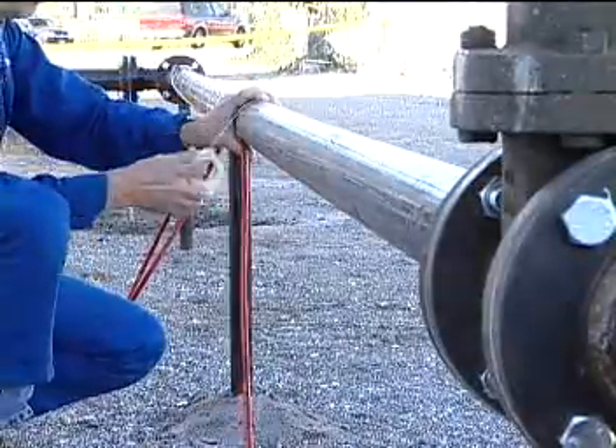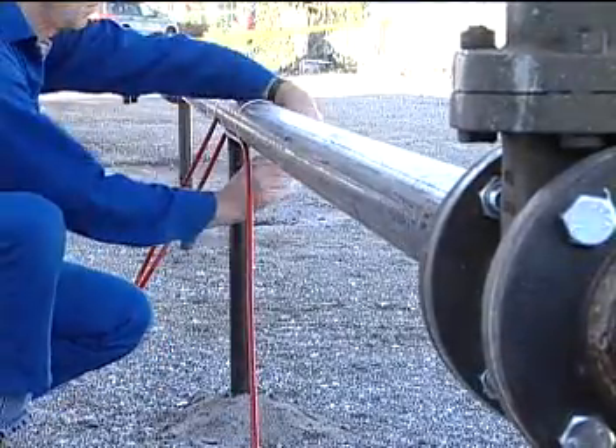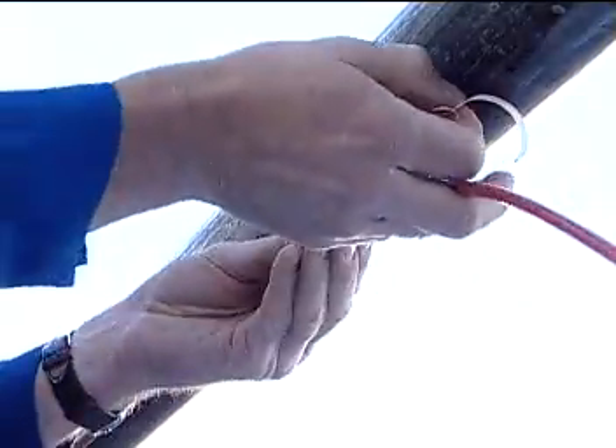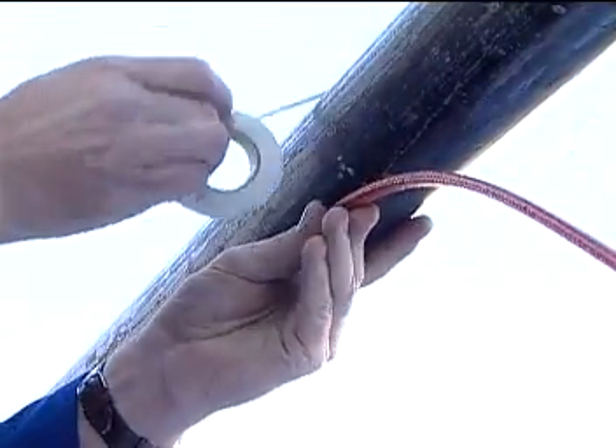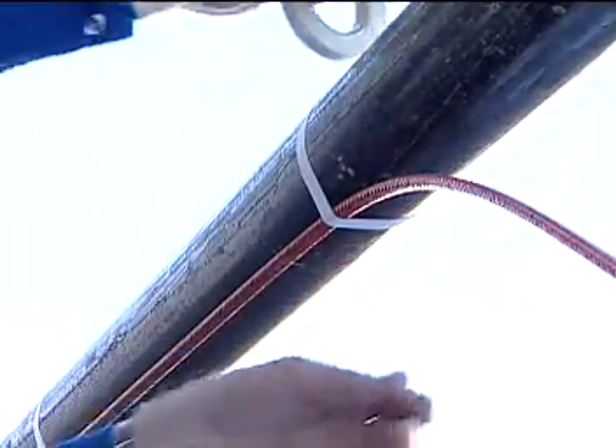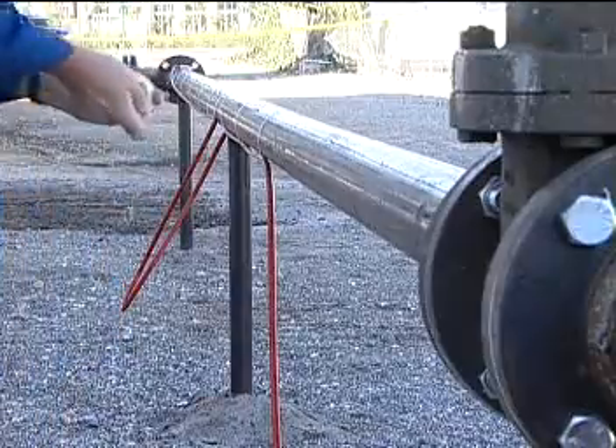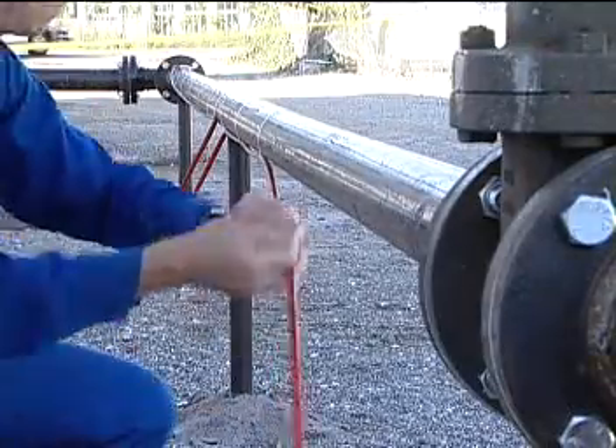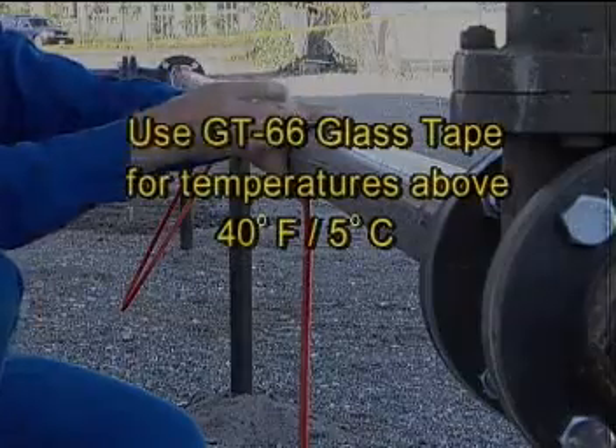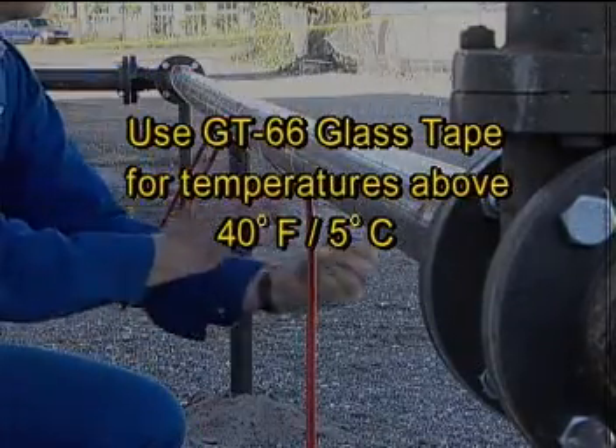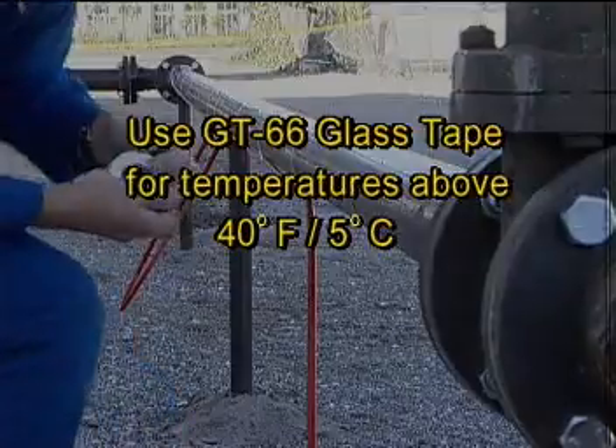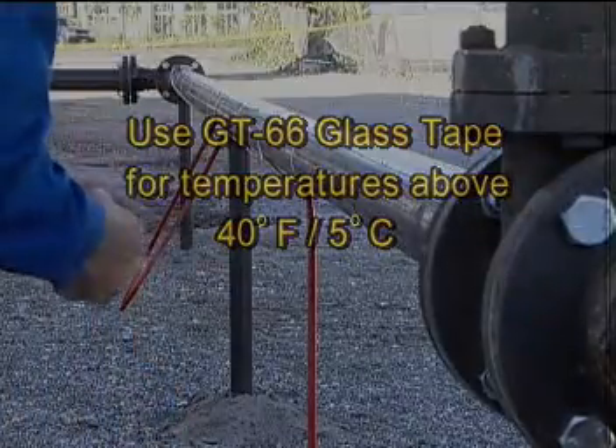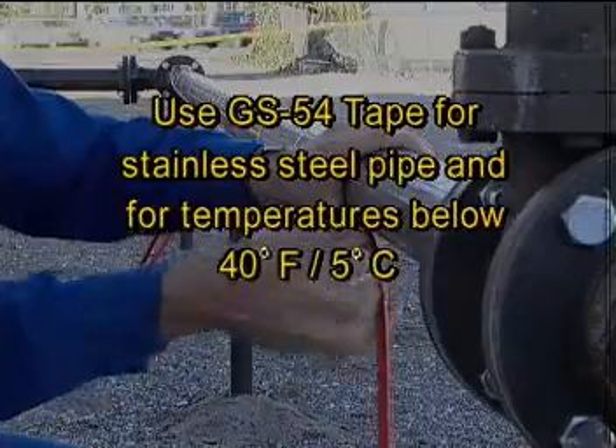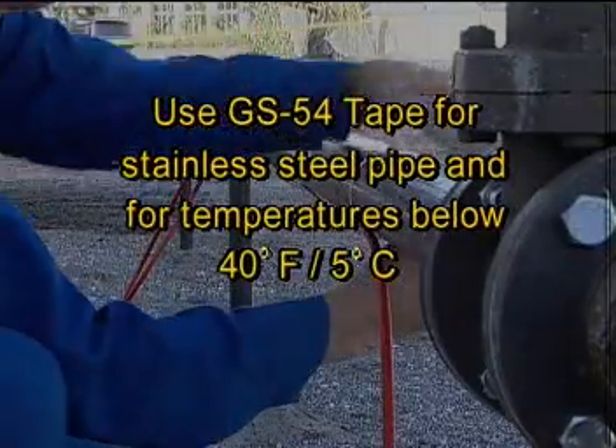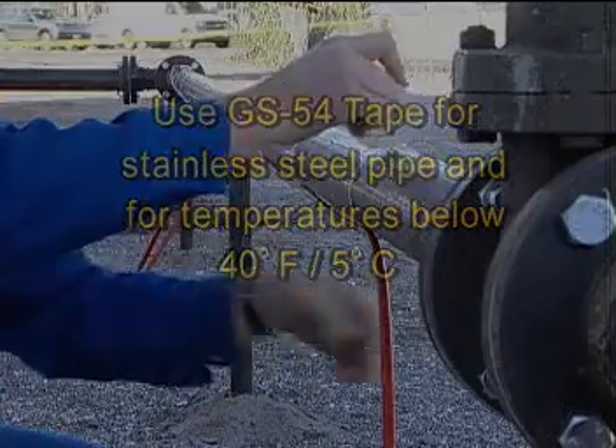When you're installing the cable in a straight line, mount it on the bottom half of the pipe. This protects it from mechanical damage and places the cable closest to the product in the pipe. For installation, start at the end and work your way back toward the reel, securing the cable to the pipe at least every 2 feet with the glass tape that's provided with the heating cable. Use GT66 glass tape for installation temperatures above 40 degrees Fahrenheit, 5 degrees Celsius. Do not use it on stainless steel pipe. Use the GS54 for stainless steel pipe and for installation temperatures below 40 degrees Fahrenheit, 5 degrees Celsius.